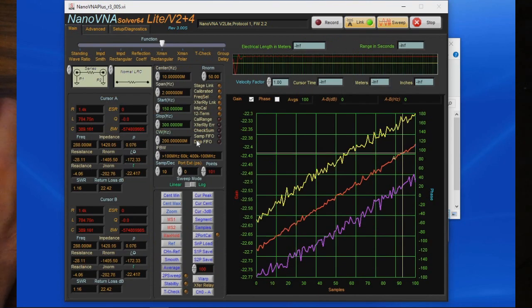There's two different error statuses for the FIFOs. One of them is for the sampling FIFO, the other is for the display FIFO. So the way the software works is it has one thread that's just basically collecting the data off of the Nano. It then forms a packet or a whole sweep. Once it has that, it loads that into another FIFO, which gets passed off to the main thread, and then the main thread plots the data. So if, for example, the display were to slow down, it's possible that it would overflow this display FIFO. Likewise, if that were to slow down, it's very possible that the sampling FIFO could also overflow. The fact that we're not seeing those turn on, there's no issue with the software keeping up at this rate.